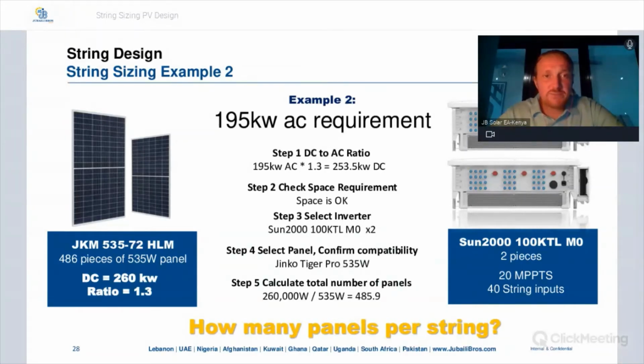Number 2, check the space requirement. We've checked and there's enough space. Number 3, select the inverter. In this case, we would probably recommend 2 pieces of the 100 KTL inverter. So 2 inverters, 100 kilowatts each, so you actually get 200 kilowatts AC capacity.